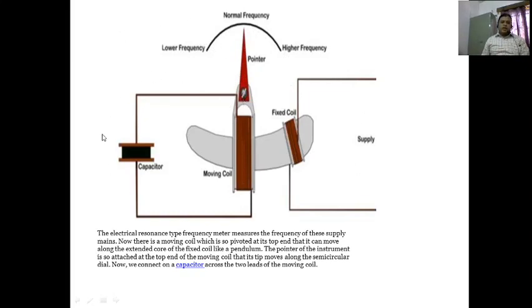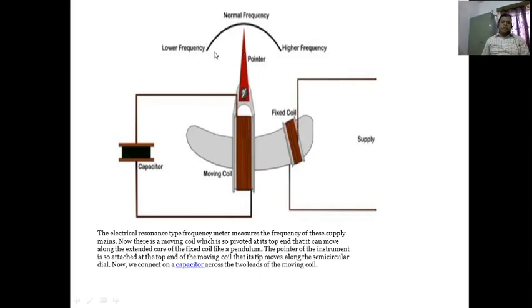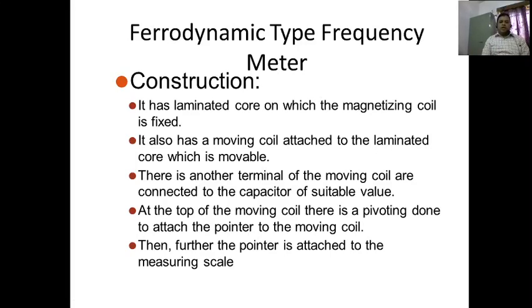With this construction and working, the electrical resonance type frequency meter measures the frequency of the supply mains. The moving coil is pivoted at its top end and can move along the extended core of the fixed coil like a pendulum. The pointer of the instrument is at the top end of the moving coil and its tip moves along a semi-circular dial. We connect a capacitor across the two leads of the moving coil.